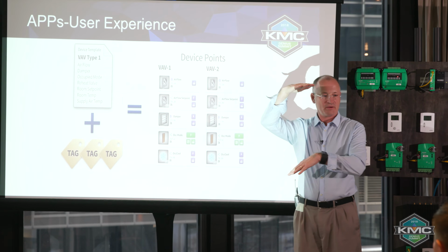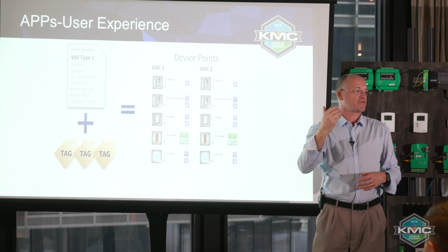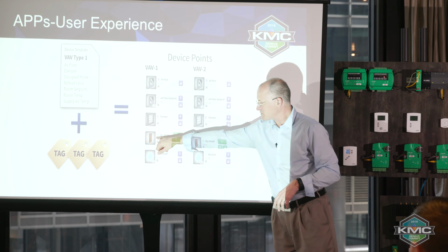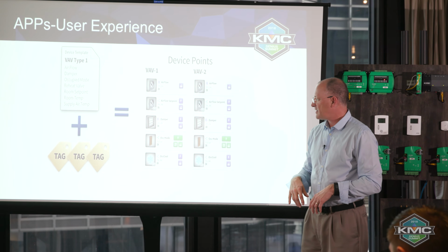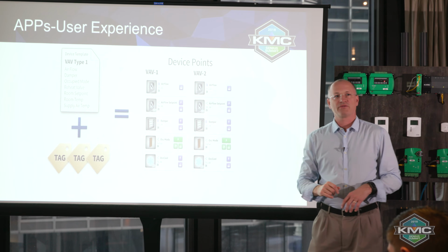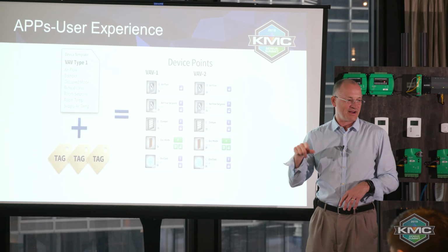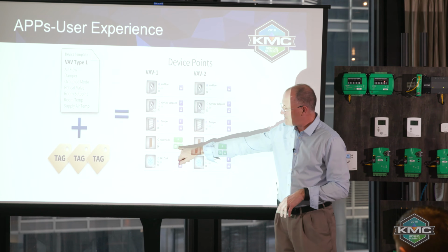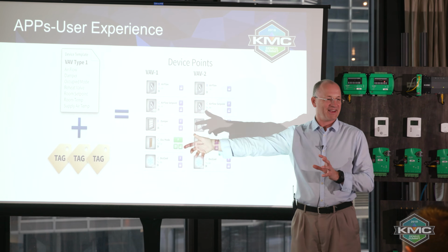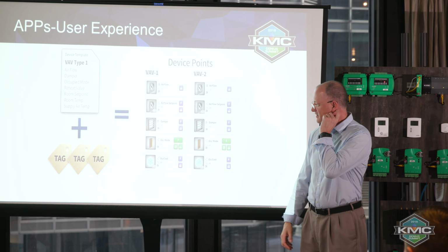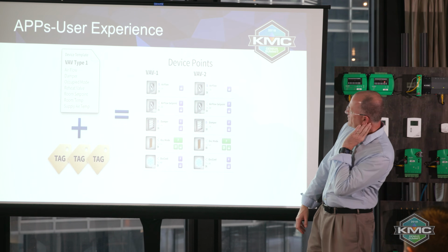You'd get your commands: emergency override, manual override, or auto. And this one's a schedule object. I think that one is looking for a schedref, a reference tag called schedule ref. But when it sees that, it makes a hyperlink to another application. Instead of a pop-up, it's linking you over to the schedule editor. And I think there's one other cool thing that goes on.